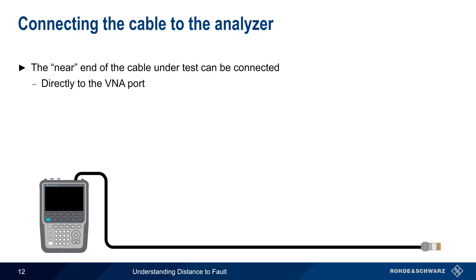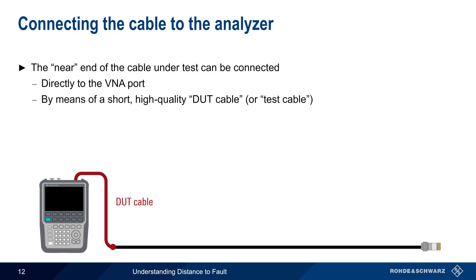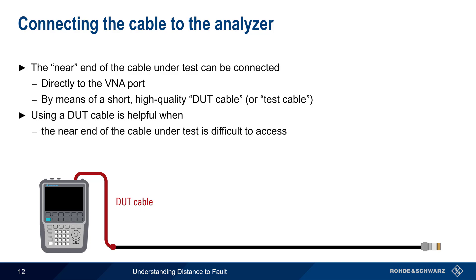When making DTF measurements, the near end of the cable under test may be directly connected to the analyzer output port. However, in many cases the cable is connected to the VNA by means of a DUT, or device under test, cable — usually a high-quality, phase-stable cable about 1 meter in length. Using a DUT cable can be helpful when the near end of the cable is difficult to access, and it can also help reduce strain on the instrument connector. A process called calibration can be used to remove the effects of this DUT cable from the measurement results.